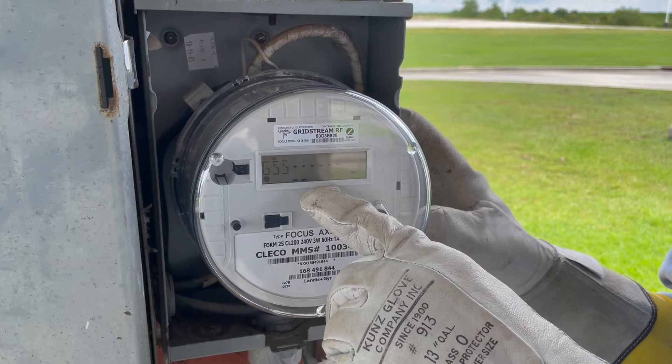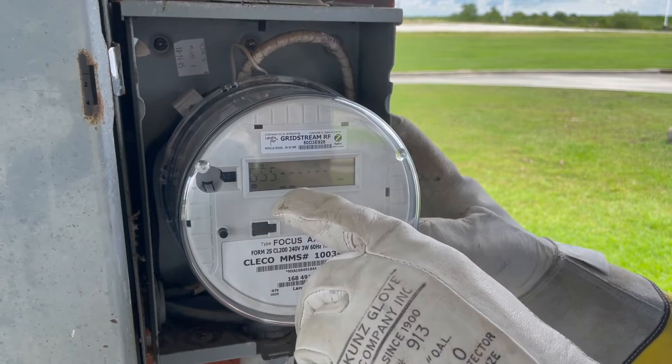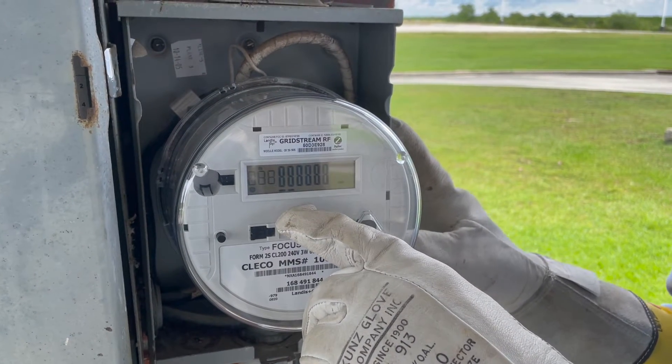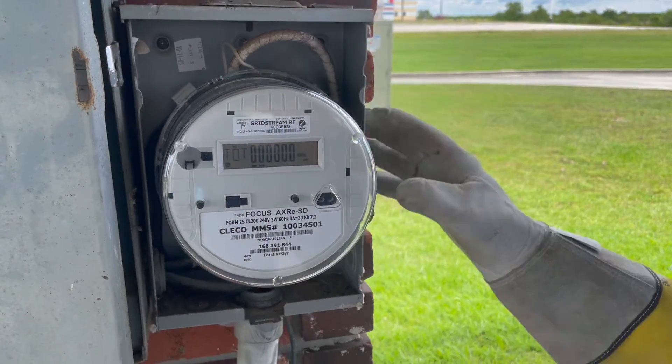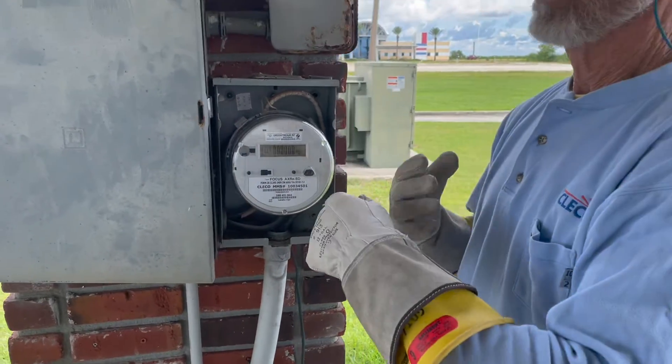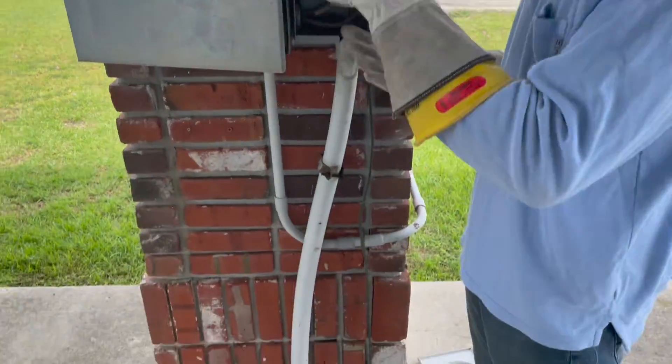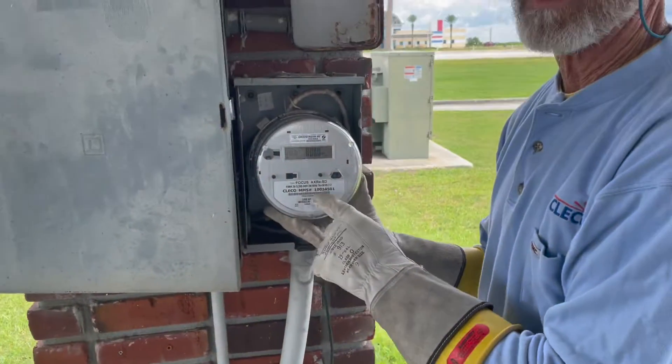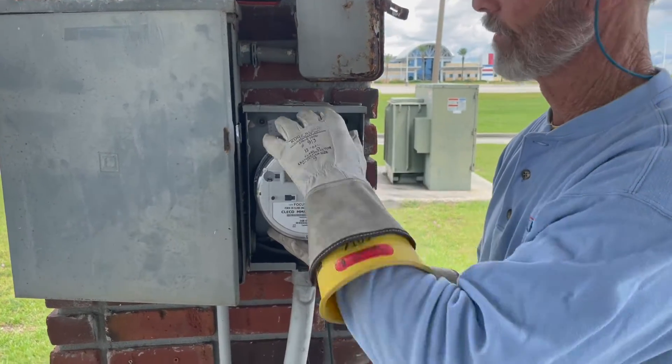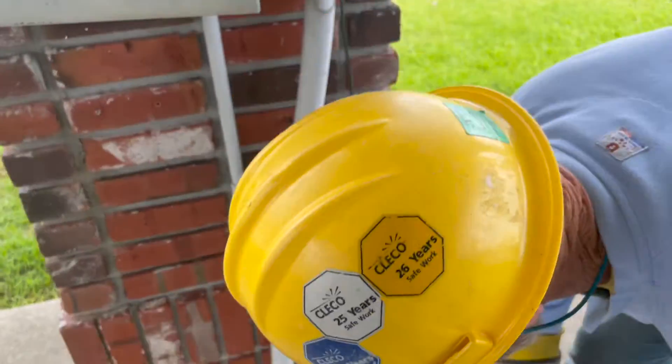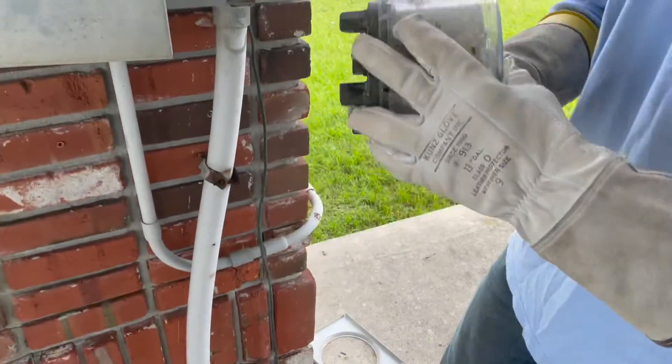This meter will meter, but it'll only meter like 86 percent because of the vectors, the way the phase angle vectors fall in on this type of meter compared to the 12S meter. So this is the incorrect application to the meter, but the meter does light up when you plug it in.